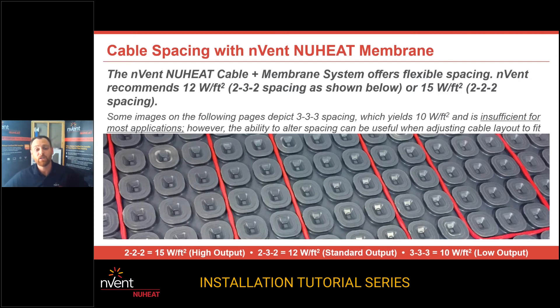If you want 15 watts a square foot, you're going to go every two pillars. If you want 10 watts a square foot, you're going to go every third pillar. That 10 watts a square foot spacing is not recommended in the Northeast or anywhere where it's cold. I would stay away from 10 watts a square foot. Our national average, what we've been using for over 30 years, is 12 watts a square foot, which you can get with NUHEAT cable and membrane at 232 spacing.